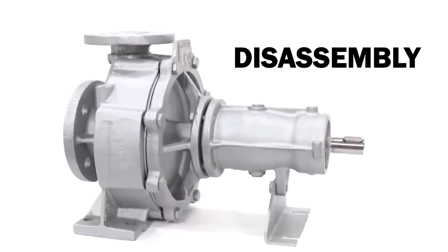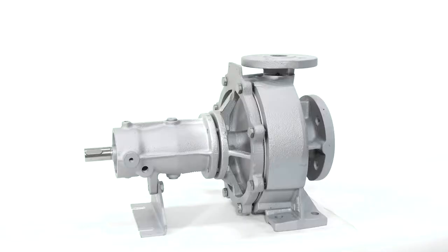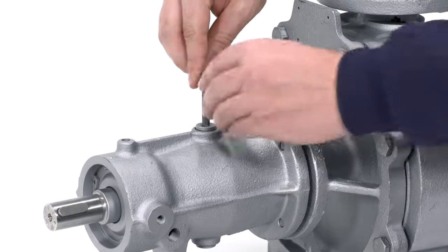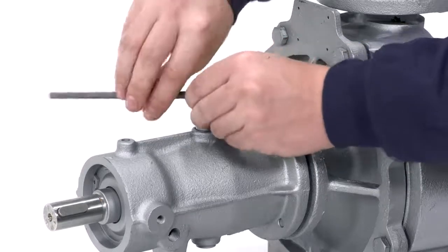Pump disassembly: Place the pump on a workbench horizontally in order to drain any remaining oil. Remove the vent and fill plugs using a 6mm hex key and drain the oil from the bearing housing.